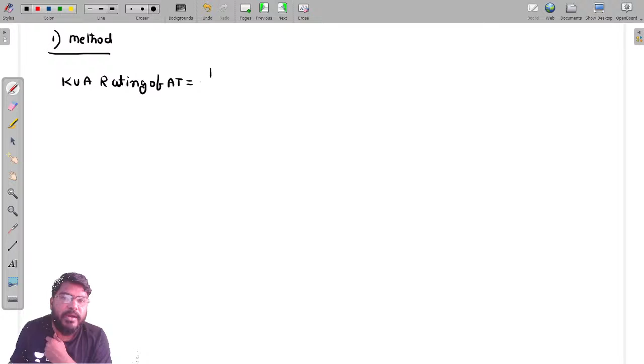Now let us find out the first method. This is method 1. I will discuss all the possible methods. KVA rating of auto transformer is equal to 1 by 1 minus K times the KVA rating of the two winding transformer.